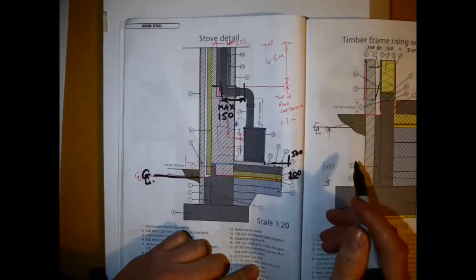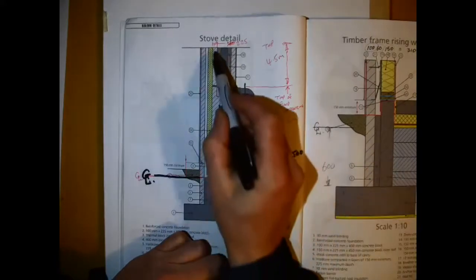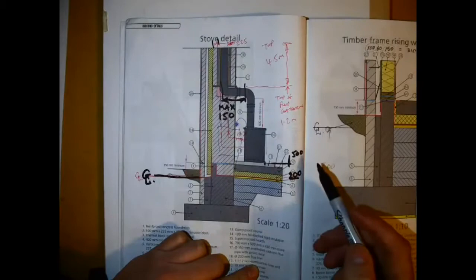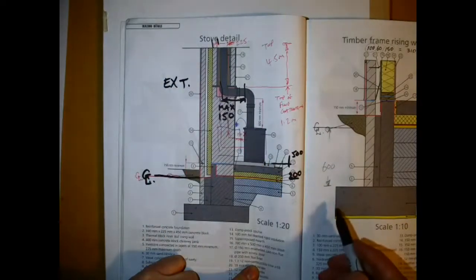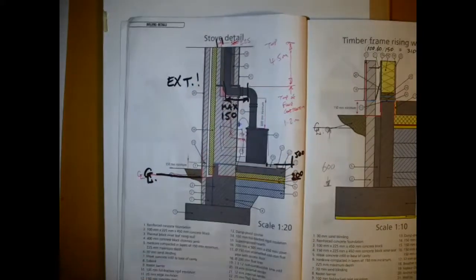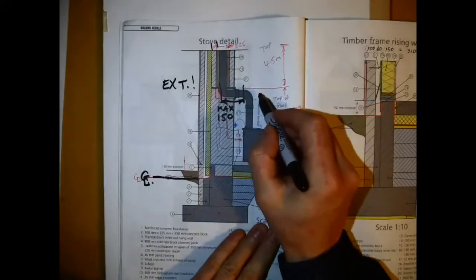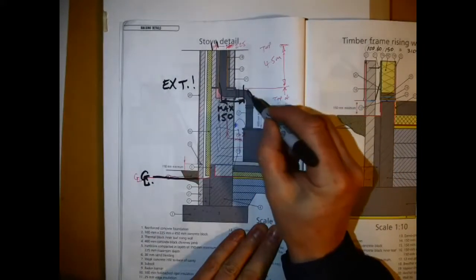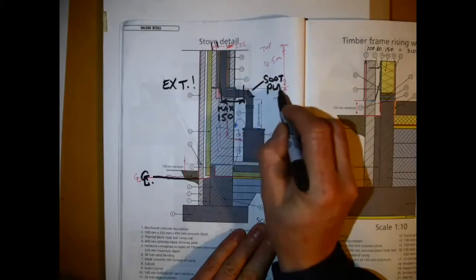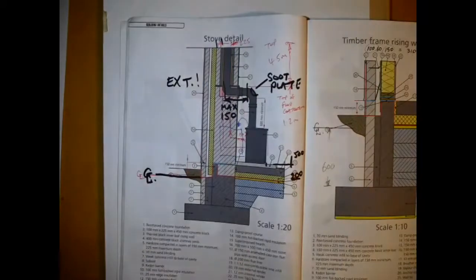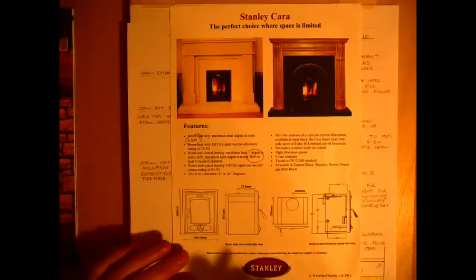So the other thing that it has on it here would be kind of going back to old cookers and that sort of thing, where it would be a soot plate for cleaning the flue. You've got a 100mm wall or block wall at the end going to an external wall, so you may get away with it in this one here. The soot plate, though, would have been a feature on the internal walls of cookers and that sort of thing, and just used for access to clean, which will be okay. But again, we're getting into territory where there's too much of a run. If that had been angled, you would get away with it, but with the horizontal run you wouldn't.